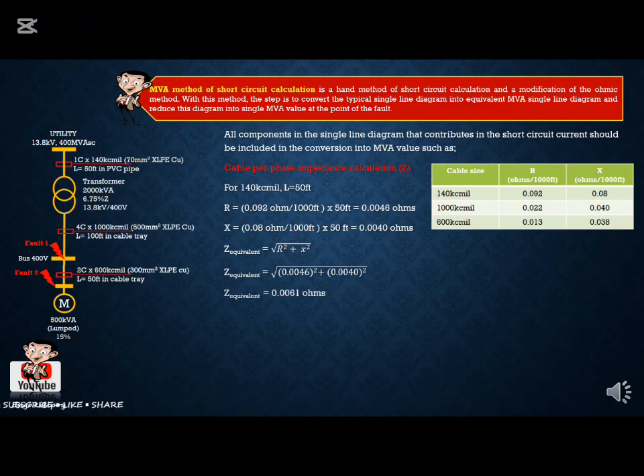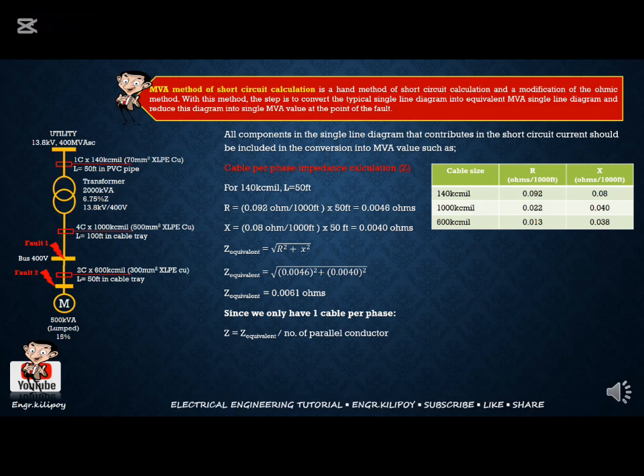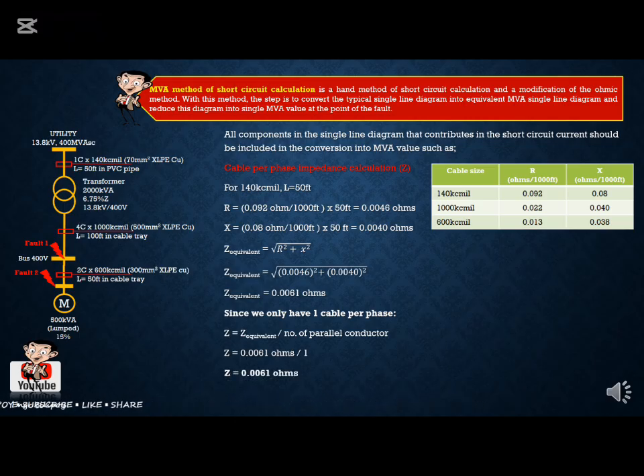So we have 0.0061 ohms Z equivalent per cable lang yan. And since we have one cable per phase, our per phase impedance will be the equivalent impedance per cable divided by the number of parallel conductors. So we have 0.0061 ohms divided by 1, which is 1 core per phase. So we have 0.0061 ohms. Ito yung value ng ating per phase impedance ng 140 kcmil.